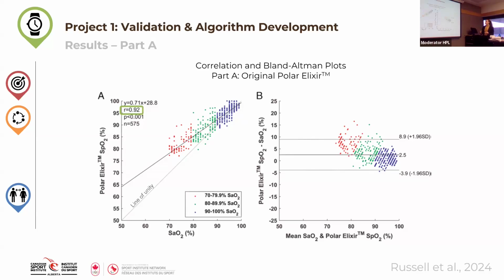And now, going over to our Bland-Altman plots. We've got the mean of our two measures on the x-axis, and the difference between the two measures on the y-axis. We can see that the red dots denoting that 70 to 80% SaO2 are above that mean difference line, showing that we're overestimating pretty regularly on that end of the scale. And our mean difference is about 2.5%. So the SpO2 monitor seems to be overestimating oxygen saturation, on average, by 2.5%.